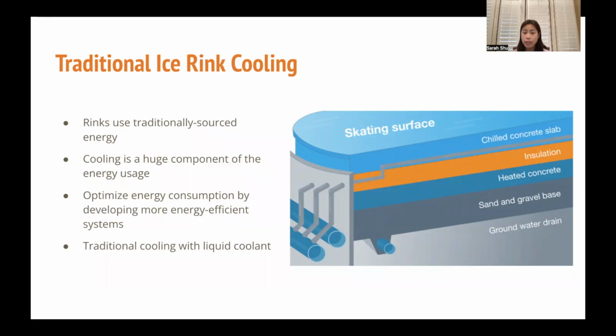The traditional cooling system uses a fluid with a lower freezing point than water to remove and divert heat from the ice rink. Typically, this involves running liquid refrigerant at -9 degrees Celsius through pipes laid underneath the surface of the ice. The liquid draws heat from the ice and is fed to a chiller, which allows the liquid to remain at a cool temperature using outside air and water.